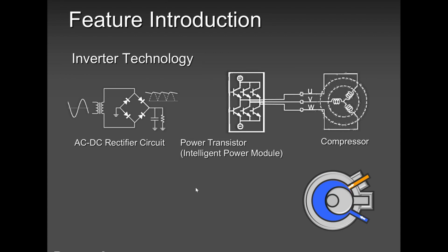Then comes the outdoor PCB. The outdoor PCB is now one whole complete box. Before, we had separate circuits. This circuit was on its own, the IPM module, the AC rectifier was on its own, the noise filter, and then we had the control board. Now we have everything together. That's a good thing, because if anything goes bad, you change the whole PCB and waste no time.